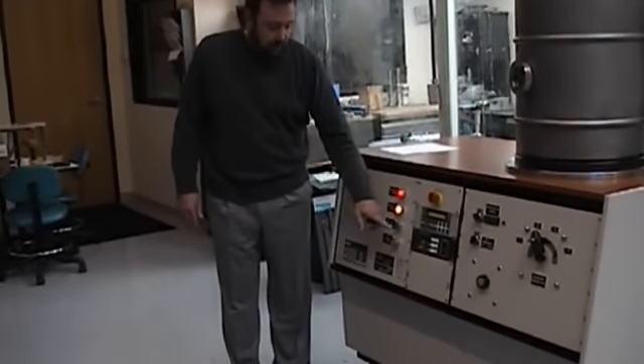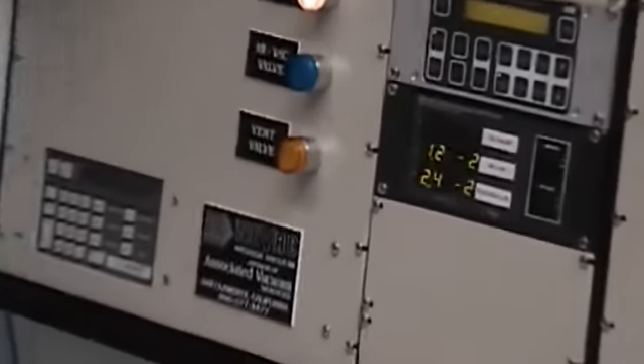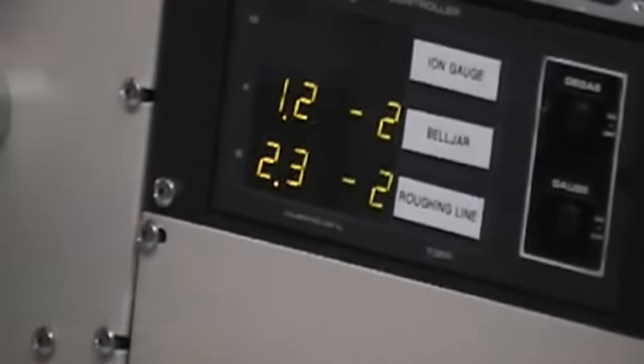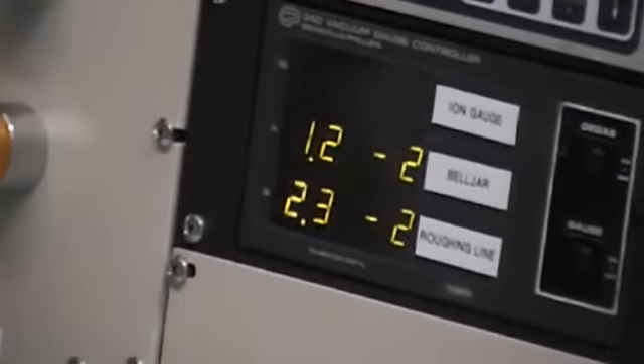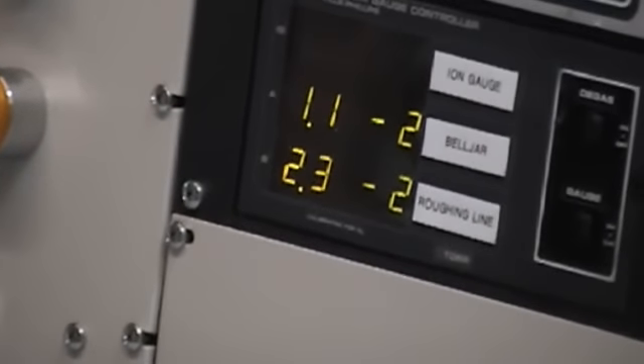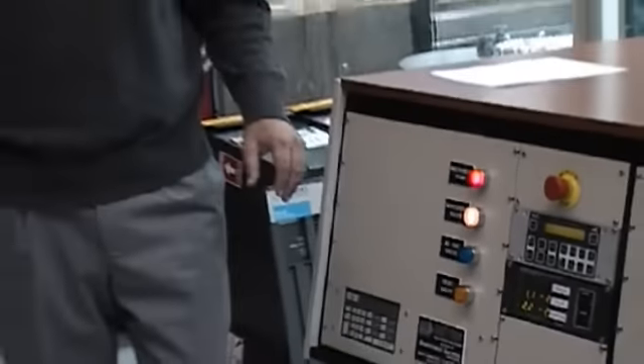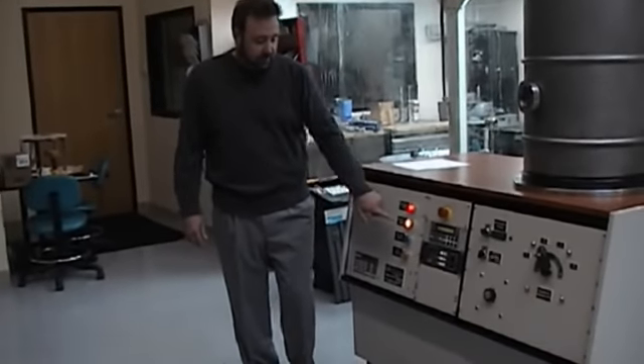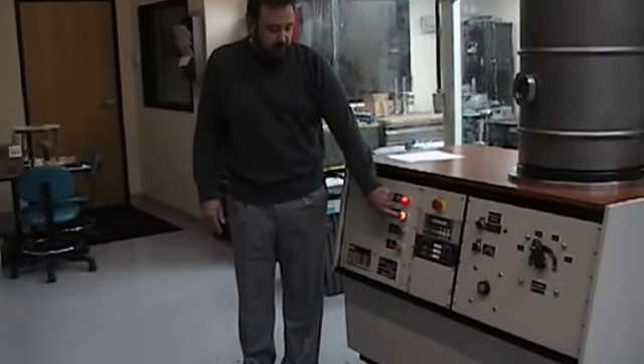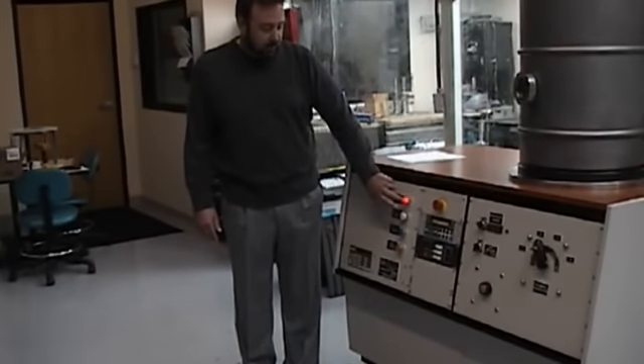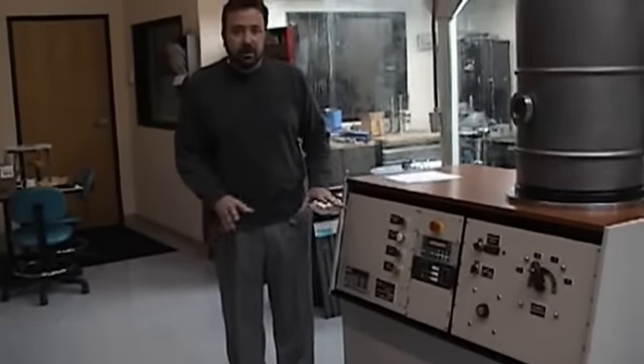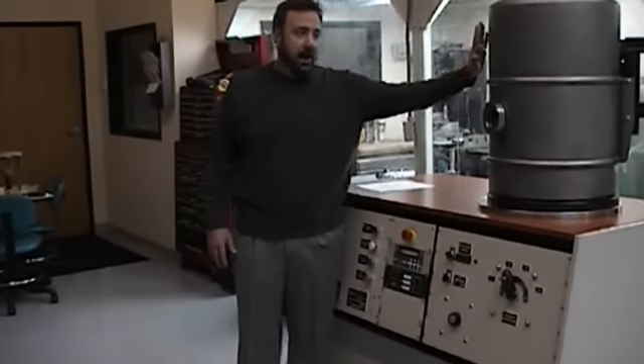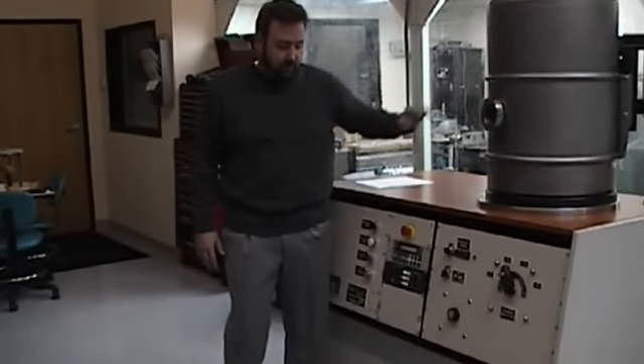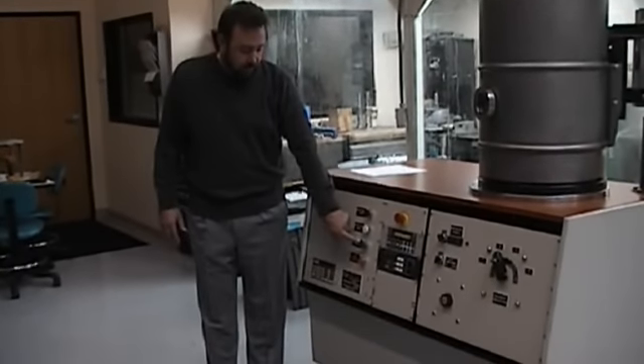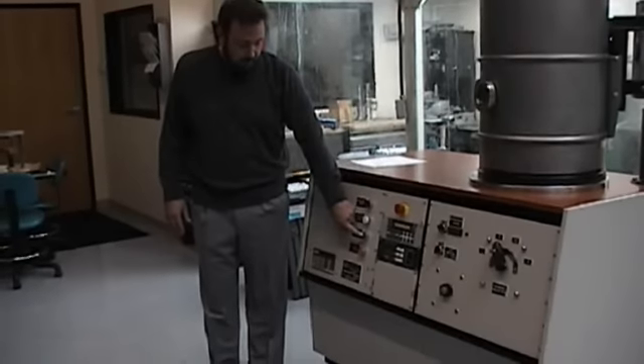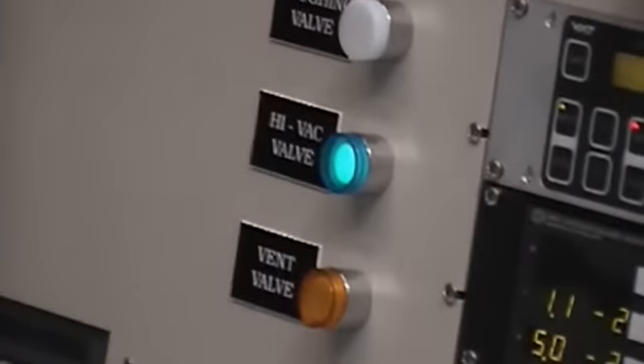So as you see, our pressures are fairly equal. 1.2 times 10 to the -2 in the bell jar, and roughly 2.3 times 10 to the -2 in the roughing line. They will eventually equalize. So for the sake of time, I'm going to go ahead and shut the roughing valve off, and then we're going to turn off the mechanical pump. They're no longer needed. We are currently at medium vacuum in this bell jar right now. What we wish to do right now, knowing that the cryo pump is cold, is open up our high vac valve.